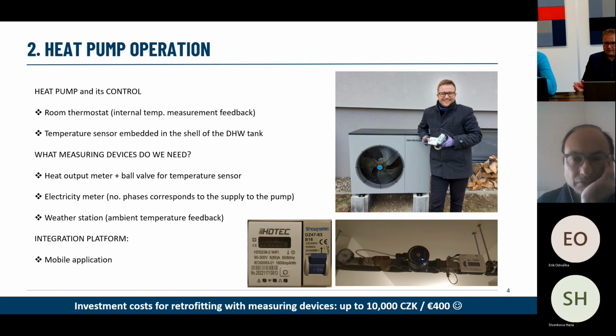So it obtains the delta T between the temperatures. It knows that you circulate water in the system, so it knows the specific capacity of the water, and it measures the flow of the water, and calculates the actual heat the heat pump delivered. We'll elaborate how this compares to the data sheet — it's quite interesting reading, as you'll discover. And then there's a simple device here on the bottom left part in the middle.